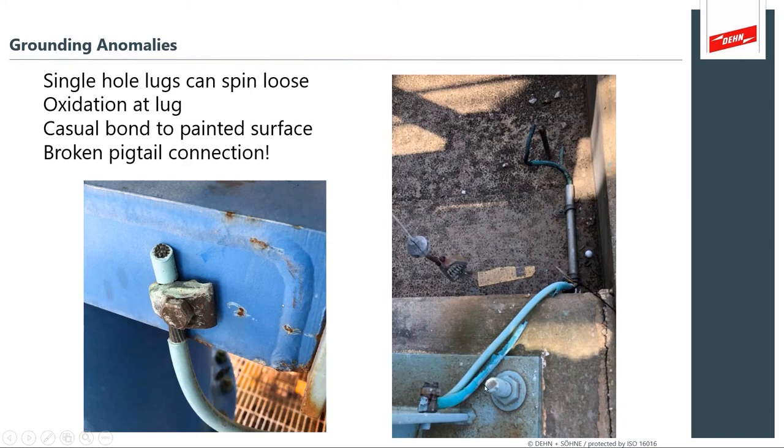These are the things that you're looking for that are going to be signposts that will tell you that you're going to have problems at these areas. And so you might be experiencing instrumentation problems and you're troubleshooting your instruments, and it's not the instrument, it's the earthing and bonding. And that's why it's really important to pay attention to these maintenance issues that you can visually inspect. These are the things that you have control of.